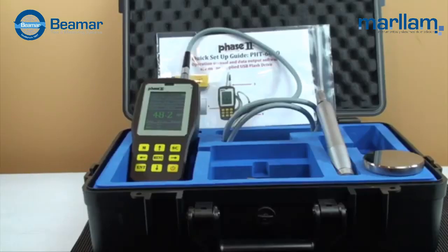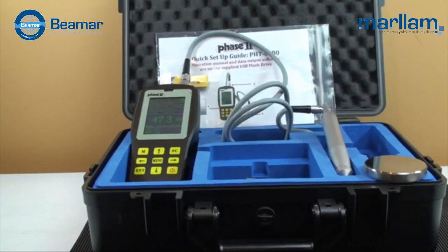This is an instructional video detailing the applications and functions of the Phase II PHT 6000 series ultrasonic portable hardness tester. The PHT 6000 is designed to test metals, primarily steels, aluminum alloys, and copper alloys. But other metals can also be calibrated and tested using known calibrated standards of that metal. Because Young's modulus is the determining factor in this technology, these open architecture testers calibrate to material type and can be read in virtually any hardness scale.